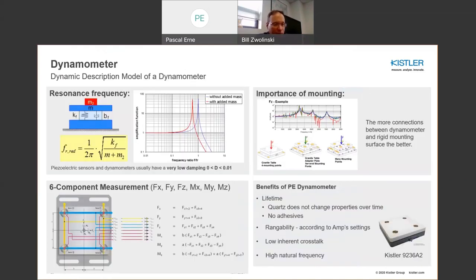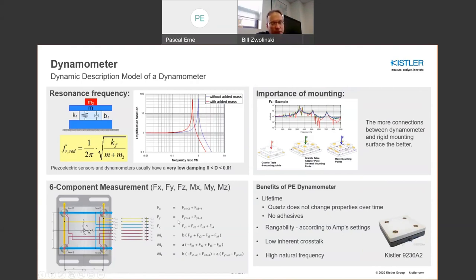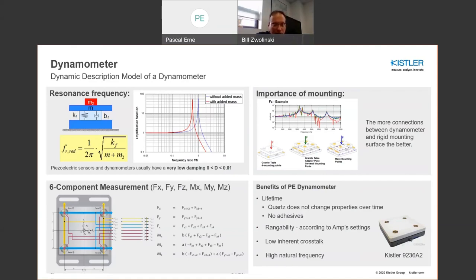Force dynamometers are spring-mass systems and mass will affect natural frequencies. For the six-component measurement, with a separation 'a' between the center of the sensor and the vertical axis, and 'b' as the horizontal separation to the center, you can write closed-form expressions to derive the six components directly. Mounting is always critical for best frequency performance — you want a very rigid mount with multiple fasteners. Piezoelectric dynamometers are extremely robust, have over-range capability, are rangeable, provide high signal-to-noise ratio, low noise, and generally high natural frequencies — making them complement this type of measurement quite well.